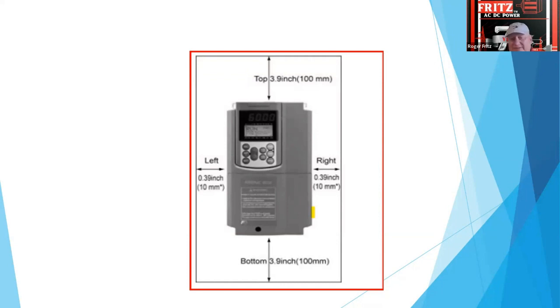especially if your supplier is supplying what they call variable torque drives. What that really means is they're taking a constant torque drive and derating it to only 120% capability, because they know that typically a pump doesn't work that way. I tend not to try to do that. I try to use constant torque drives, use them in the variable torque mode. That always gives me 150% factor on the transistors, which means the actual transistors are rated at 300% capability. So even if the guy surges them or shorts them, you won't have transistor failure.